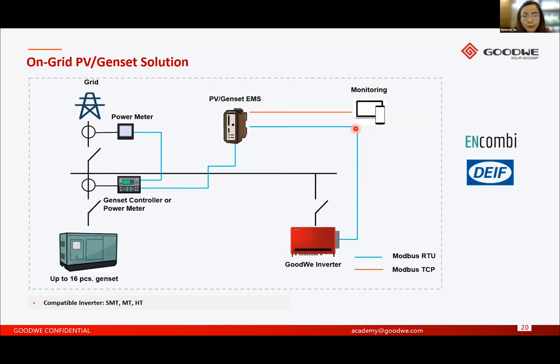GoodWe products are also very flexible to be compatible with the genset. As we can see from the system layout here, the solar inverter will be connected to the PV and genset energy management system in the center here. It is the controller of the system. So the EMS will be connected to our inverters using Modbus RTU through the RS485 cables. As a result, both the PV inverters and the genset can be controlled. For instance, functions like the on and off mode and the power output can be controlled. And our inverter can be fully compatible with the EMS of two brands called ENcombi and DEIF.